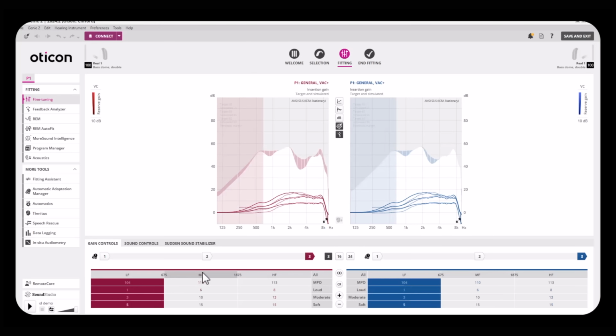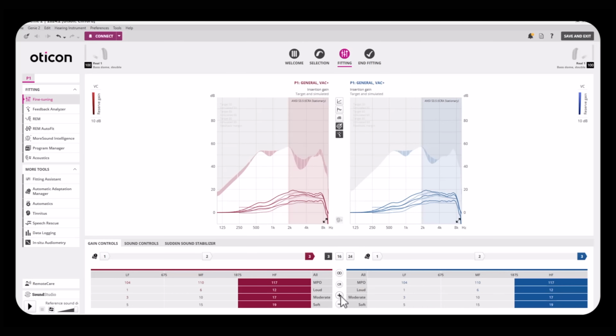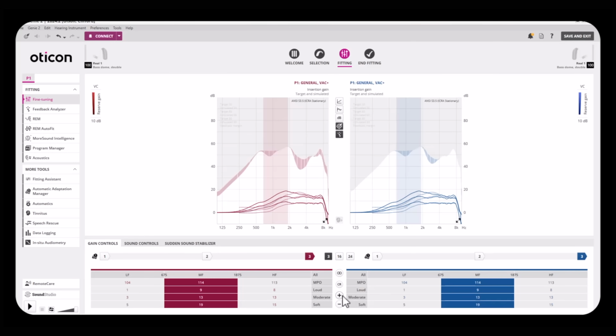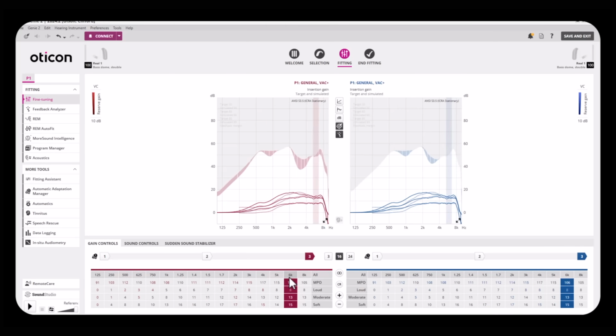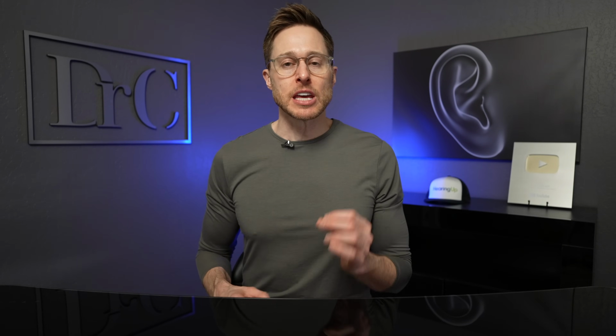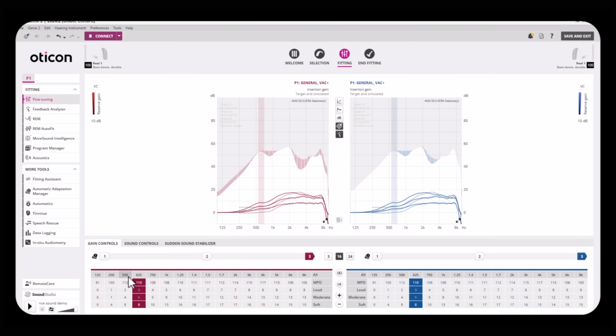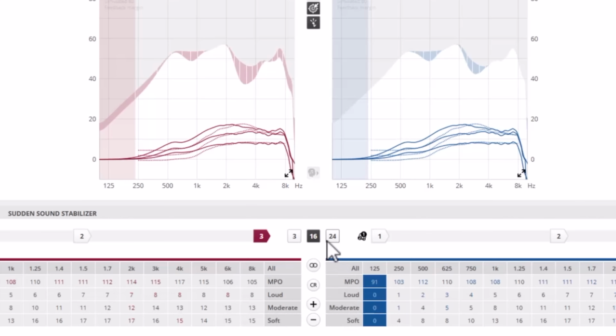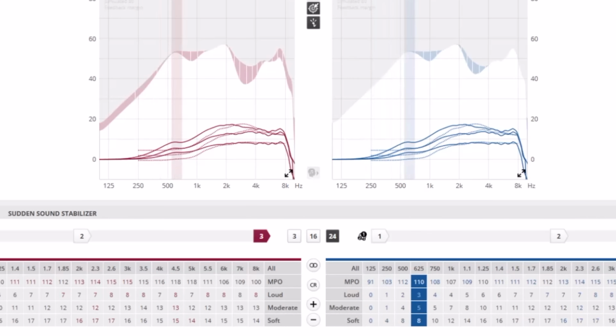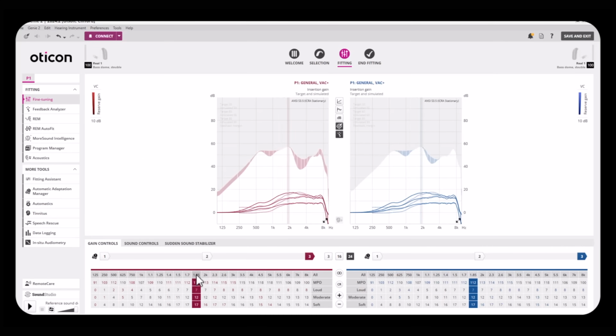If you only have a 3-band equalizer inside of hearing aid programming software, then you will not be able to custom program a hearing aid to the point where you're applying the exact right amount of amplification required at each frequency to maximize hearing aid performance. However, when you increase the number of equalizer bands inside of the programming software, it increases the precision with which your hearing care professional can match your prescriptive targets across the entire frequency range. Over the years, the number of these equalizer bands has increased to 24 inside of some hearing aid manufacturer software if you have their highest level of technology.